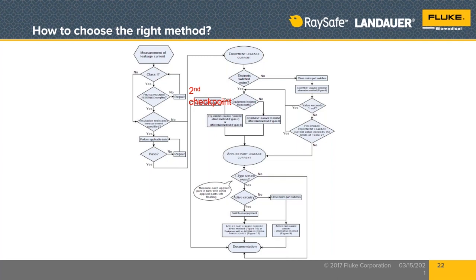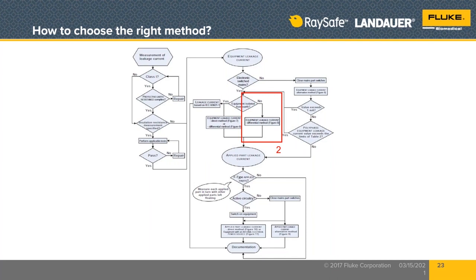Again, we're making a decision now about which testing method we are going to use to be compliant with the IEC 62353. If the device under test is not isolated from protective earth or ground, then we are required to use the differential method. Okay. If it is not isolated, we will use the differential method unless otherwise directed. So if there is no on-off switch, we use alternative. If the device is not isolated from ground, we will use differential method. If the device is isolated from ground, then we have a choice. We can use either the direct or the differential method.